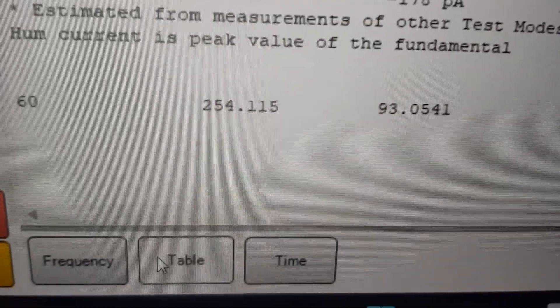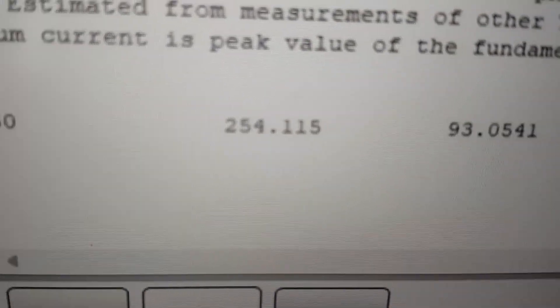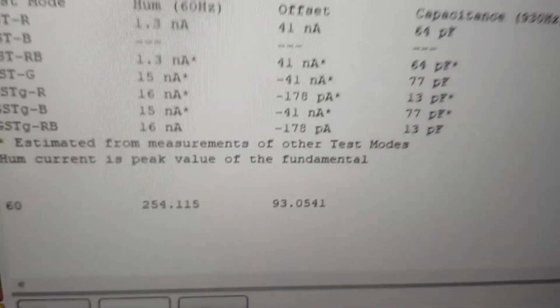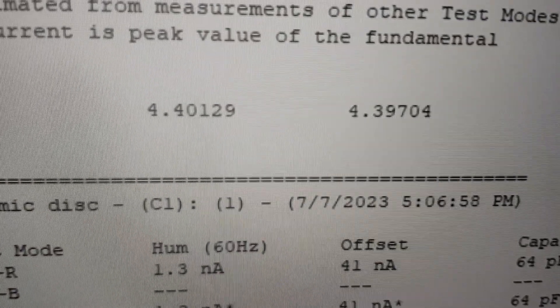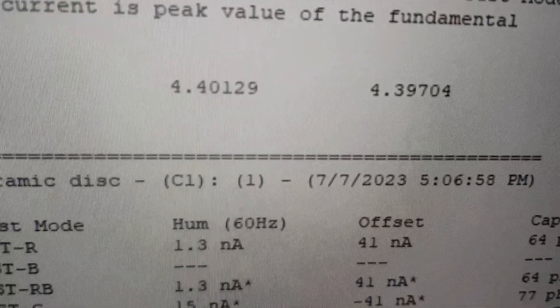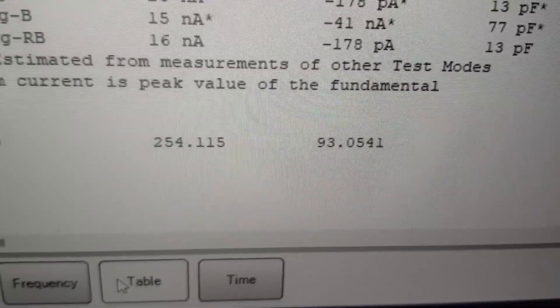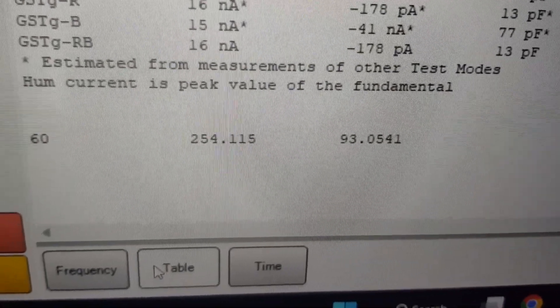Now when you look here for the unhealthy or defective insulator, the dissipation factor is 254% but the power factor is 93%. The question is: why are the power factor and dissipation factor very close when the insulator is healthy, but far away from each other when the insulator is not healthy? Please join me in this short explanation.